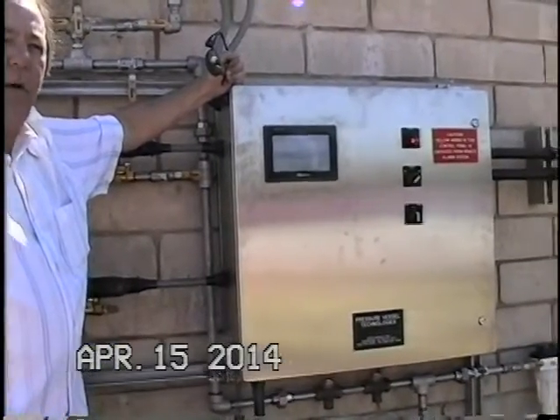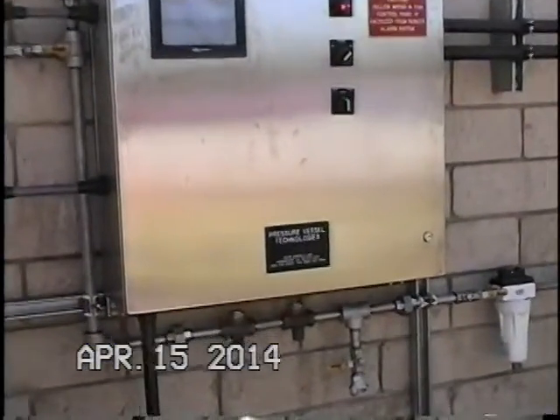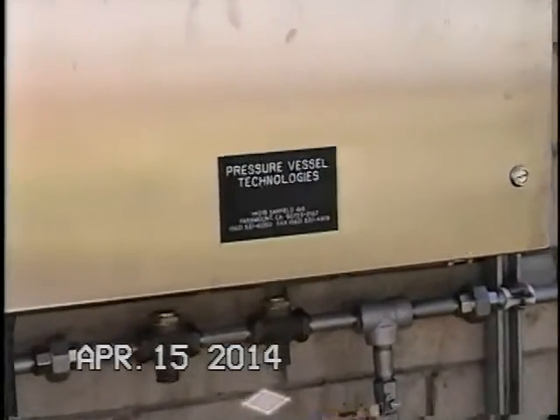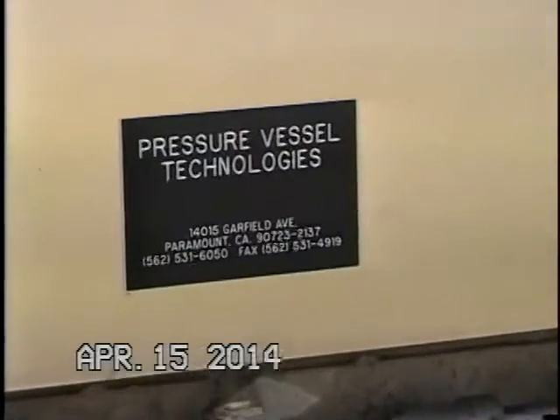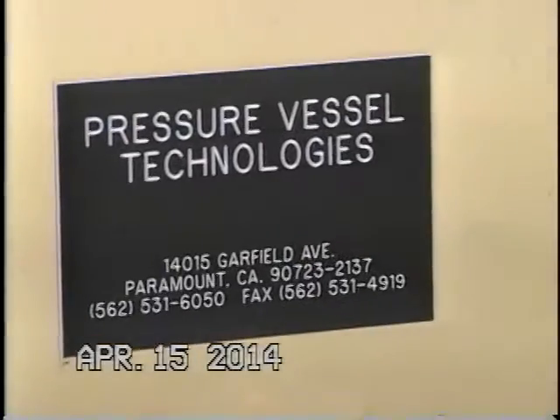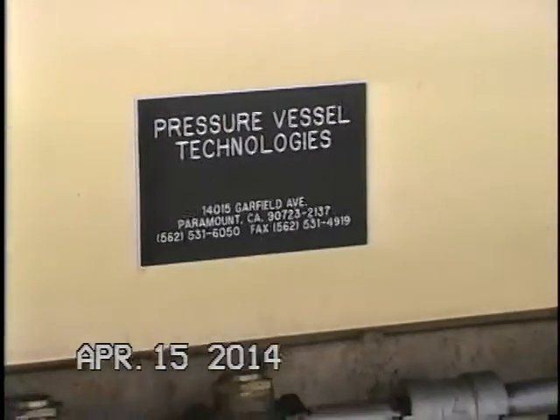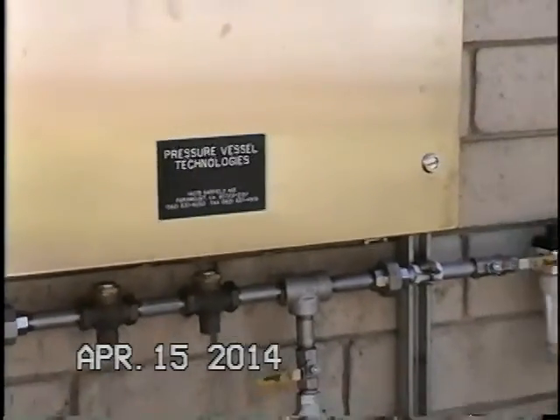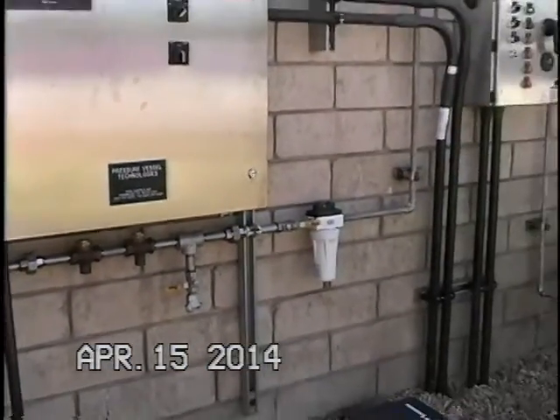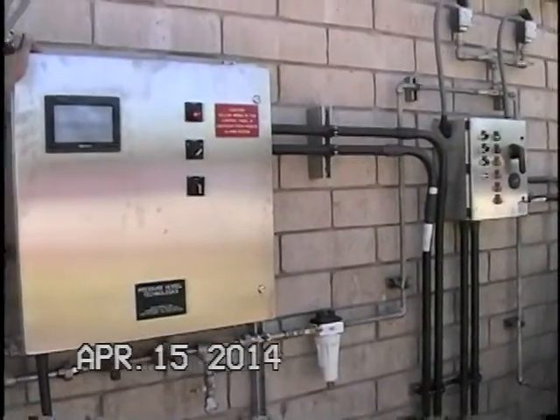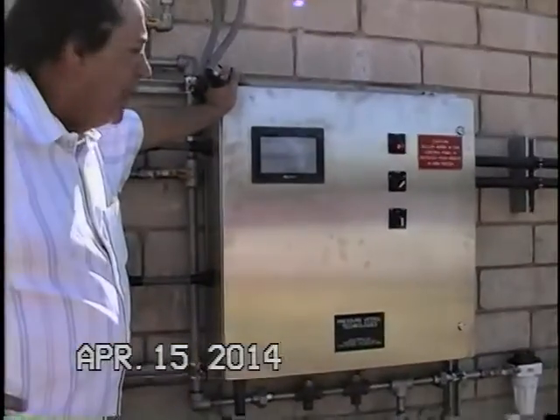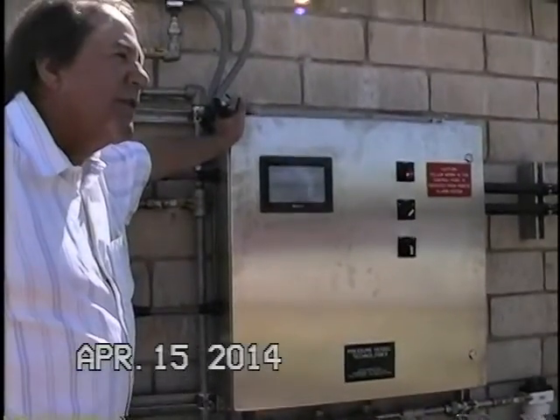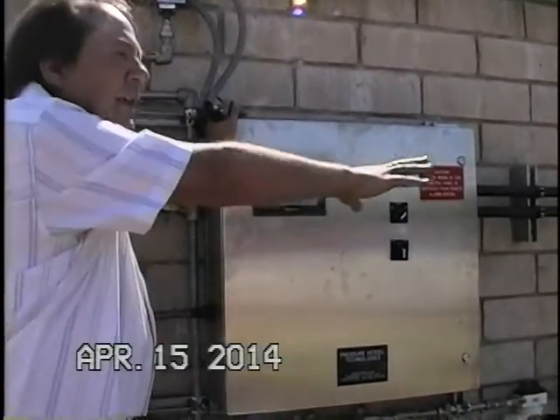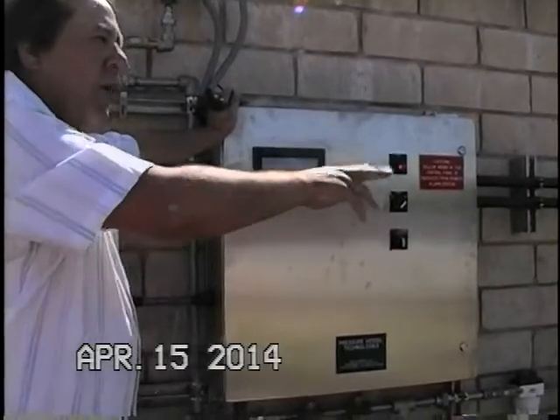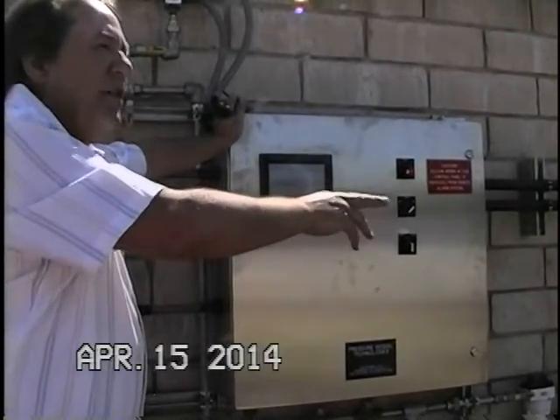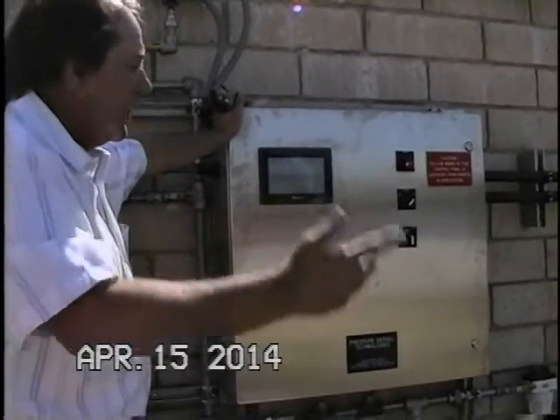Any questions so far? Yes, sir. Is that an air dryer? No, it's not an air dryer. That's an air filter. Okay. It's a coalescing filter, and it'll take any of the entrained oil. It's a 99.9% efficient filter. We use those mainly on potable water systems, where we don't want any contamination from oil condensate or anything that may be generated by the compressor. So we clean that airstream up.